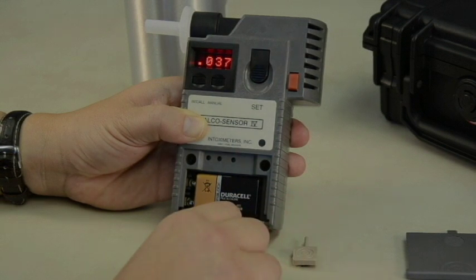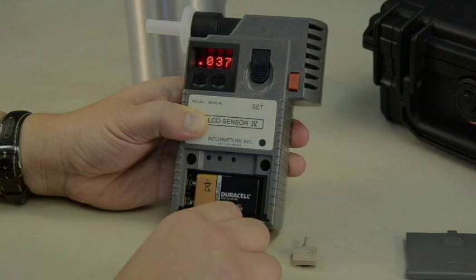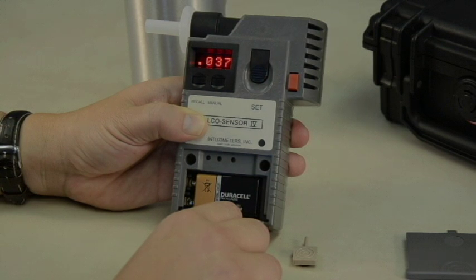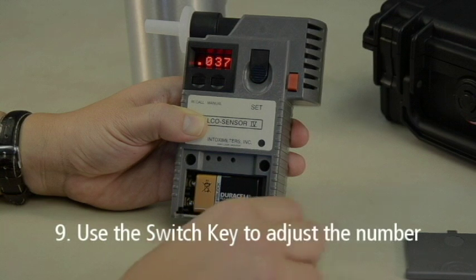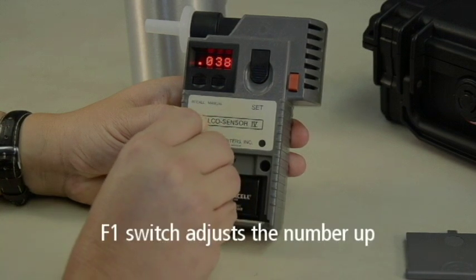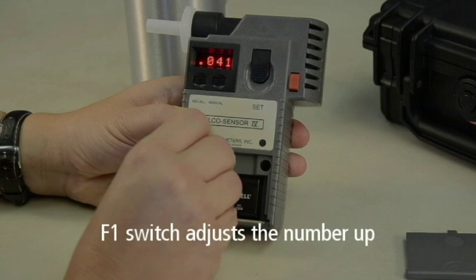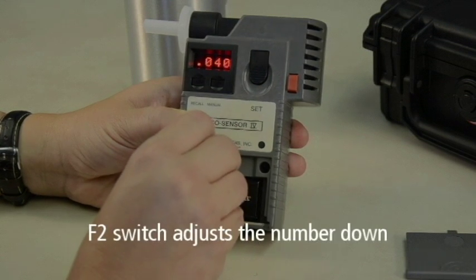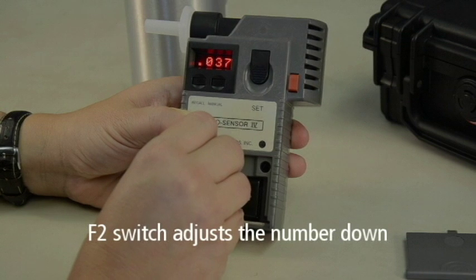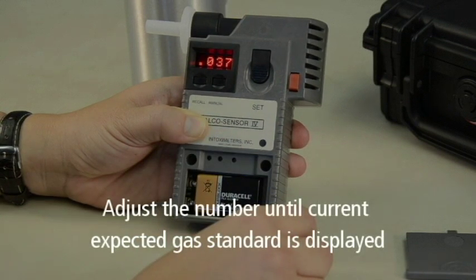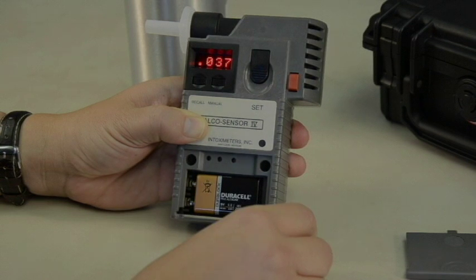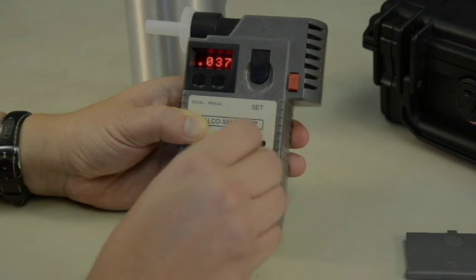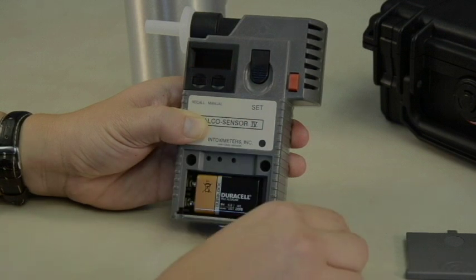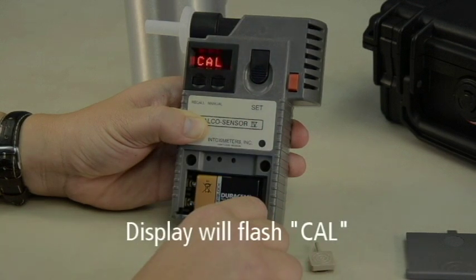If the expected value of the gas standard being used for the current calibration is different than the value of the last calibration displayed on the screen, use the switch keys to adjust the number. The F1 switch will adjust the number up. The F2 switch will adjust the number down. Adjust the number until the current expected gas standard is displayed. Once you have obtained the expected gas standard value on the display, press SET again. The display will flash CAL.